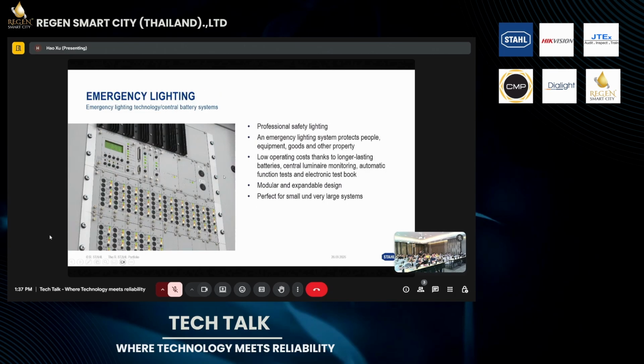We also have a so-called central battery system product portfolio, which means by installing such a central system, we need to take emergency lighting fixtures into consideration, because all the lighting fixtures can be supplied with emergency power by this central system.